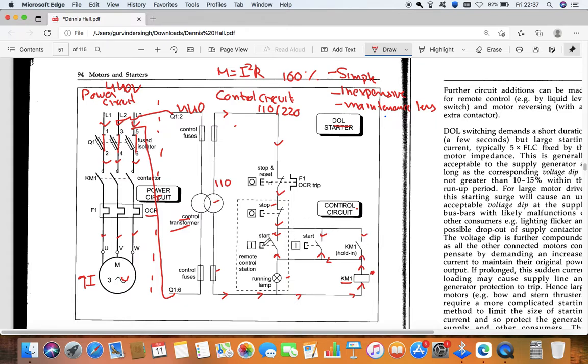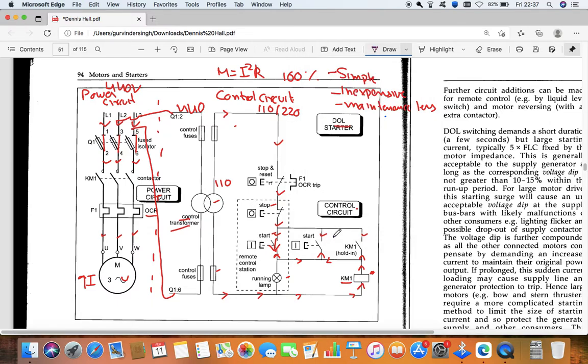Now what I will do, I will press this switch, the start switch. When I press this start switch, now you can see here, the supply is going here, here, and the circuit is completed. Okay, now you can see the circuit is completed. When the circuit is completed, this relay energizes, so it will make this contact, this, and this, and supply from here goes to the motor, and our motor starts running.